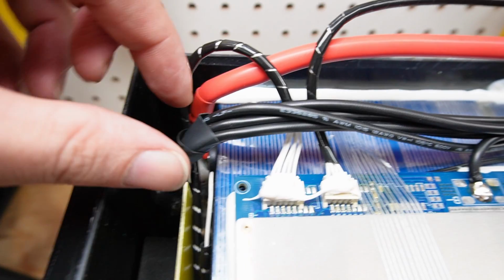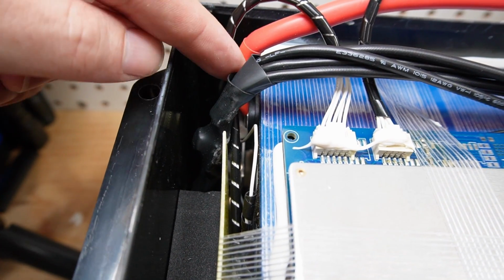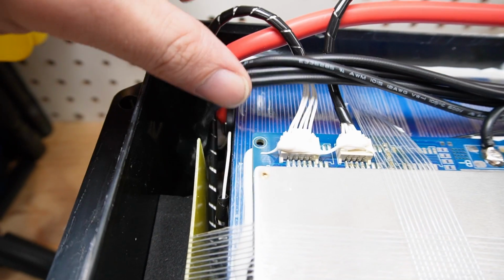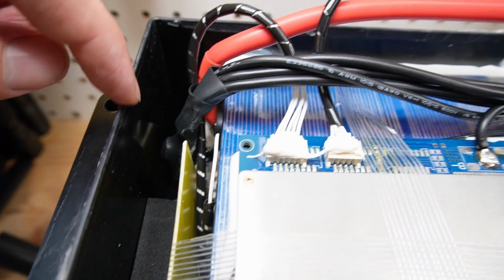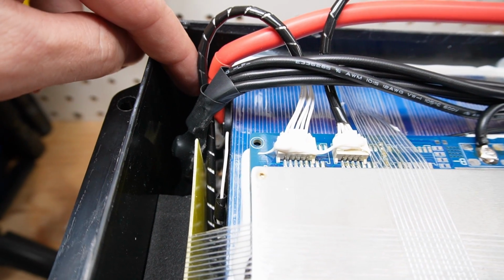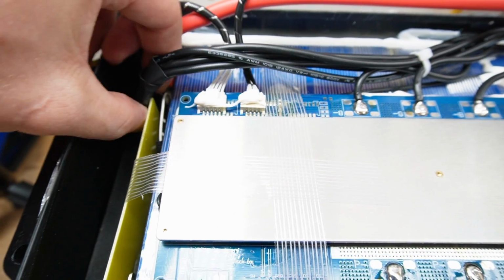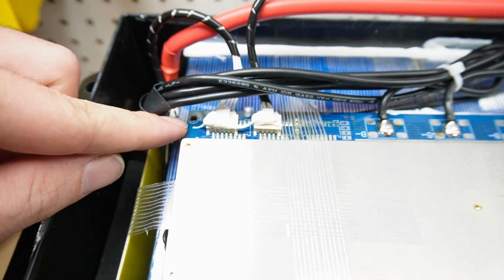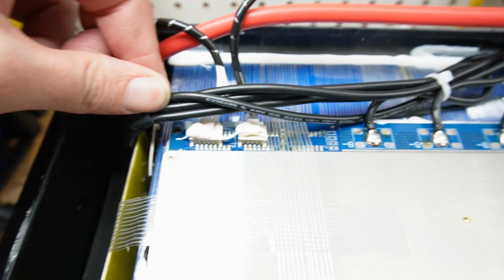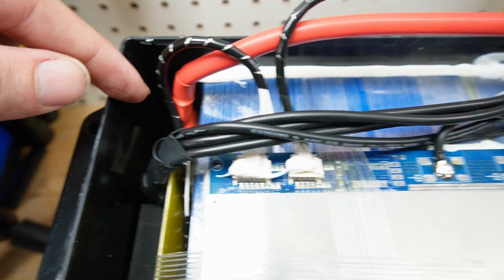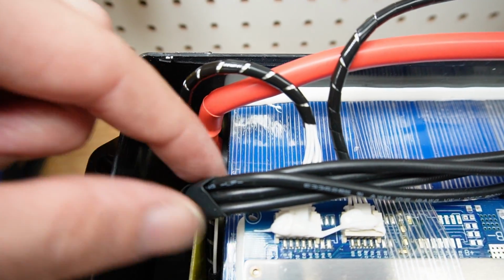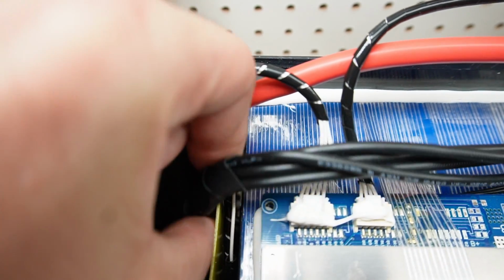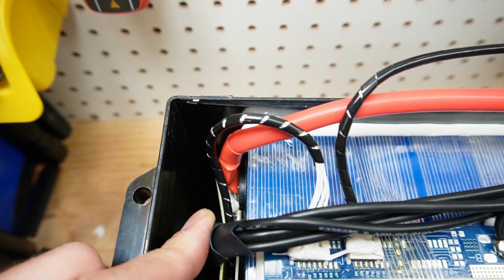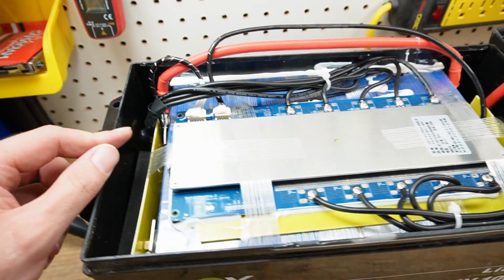Now, one thing I don't like about that is it's really close to this battery positive over here, and it can actually rub against it. So if you had vibration, that shrink wrap could rub off and then have contact with the positive terminal over here. So when I put this back together, I'm going to pull this battery cable back, and this hole here on the BMS, I'm going to put a small zip tie through it and have it here so that it can't migrate over to the positive like that. It will hold it back in this direction. That's what I'm going to do when I put this battery back together to make it safer.